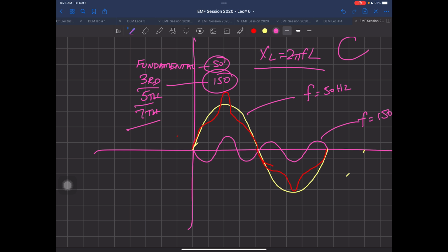So harmonics, even if they are third, fifth or seventh, whatever number, they are going to create a problem. Now practically, this is actually a mathematical way of expressing a non-sinusoidal waveform. In engineering, all four years, you will be told that all asymmetric signals will be decomposed into symmetric signals of the fundamental, that is 50 hertz in this case, then the third harmonic, then fifth, then seventh, 9th, 11th, 13th and so on. So your devices which have an inductance and a saturating BH curve will have a problem over there.